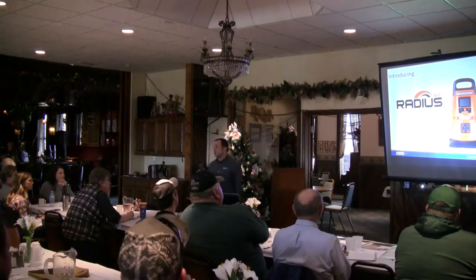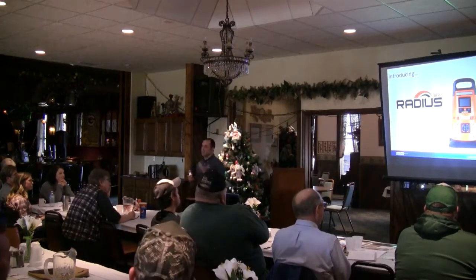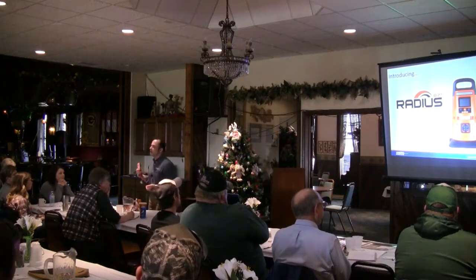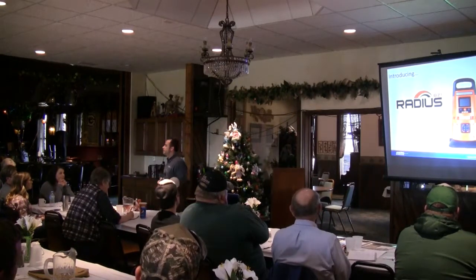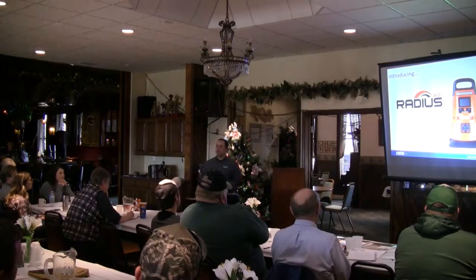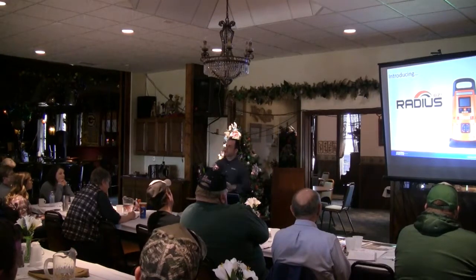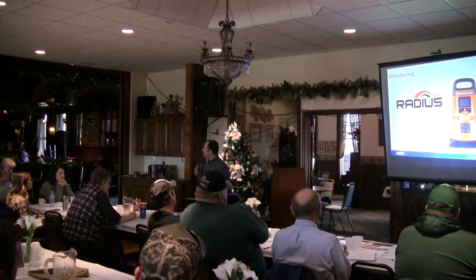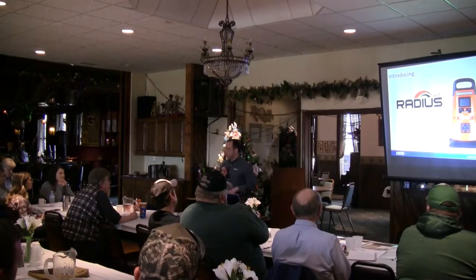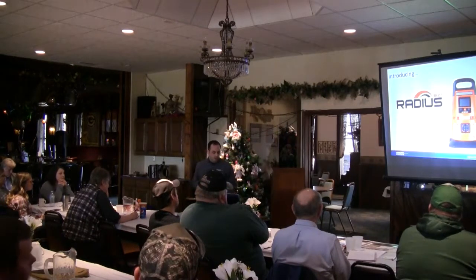The other feature mentioned earlier: as gas levels return to normal, these devices will come out of alarm. You could also force the user to acknowledge the alarm by pressing a button after they've evacuated the gaseous area. That's another option available.